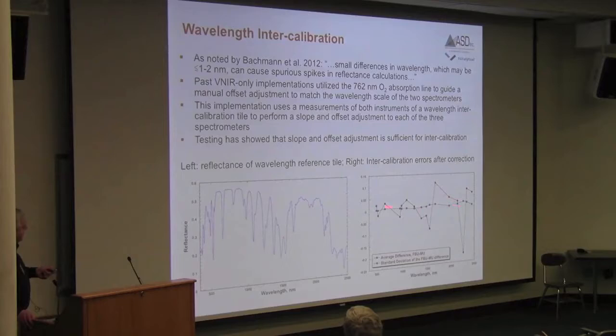So here's an example. The red dots are what the wavelength calibration mismatch between the two spectrometers looked like before we applied the slope and offset correction. And then the green, and this is an average, this was I think about 60 different intercalibrations. So the red is the average difference between the mobile unit and what we call the fixed base unit. And then the green is the amount of difference in wavelength calibration, again, at these wavelengths, after we did the slope and offset.